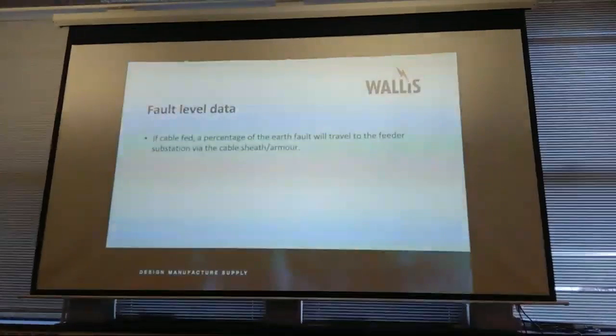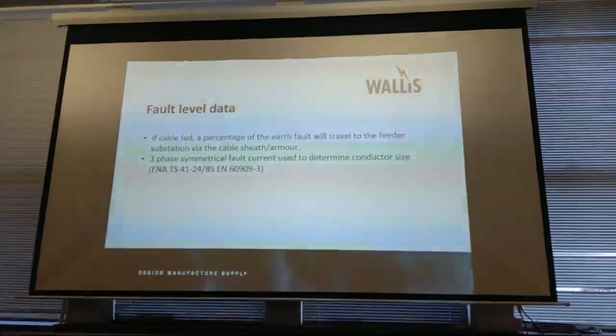Fault level data. So this is what I was alluding to earlier. If a site is cable fed and the cable sheath or the armour is terminated onto the cable box of your transformer, your RMU, whatever, that is connected, and the body of your RMU is connected to Earth, you will get a percentage of the fault going to the general mass of Earth and a percentage going up the cable sheath. I think I have got a little sketch of that.